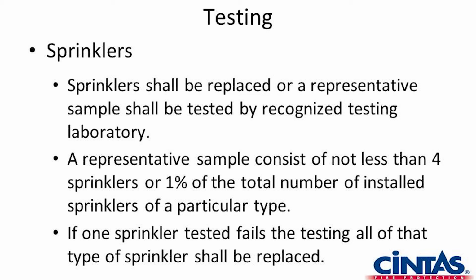A lot of companies still don't look for it because it would be new to a younger inspector, whereas an older inspector would have watched that progression and known that it is to be. But at 20 years, we would have to send those off for testing. After the first 20 years, then every 10 years from that point, they have to be tested. So heads 40 years old, we would have tested at 20 years, 30 years, and then 40 years.